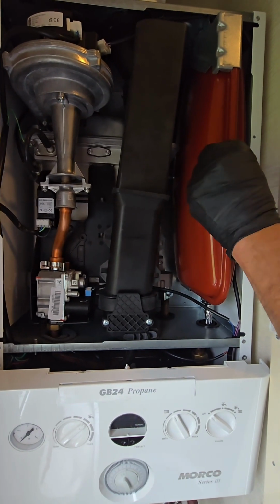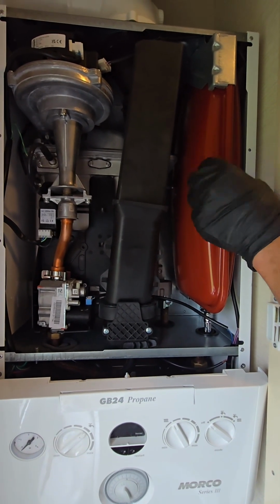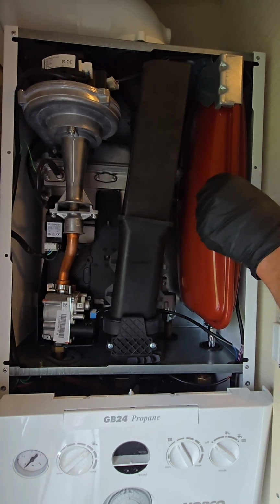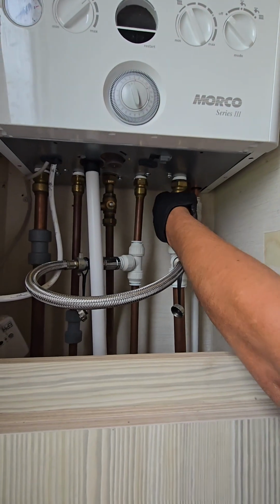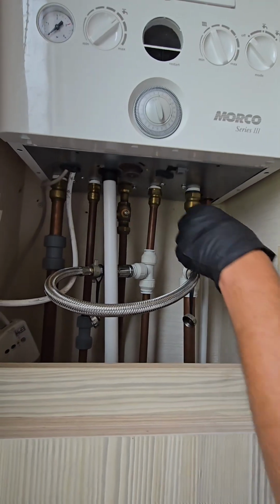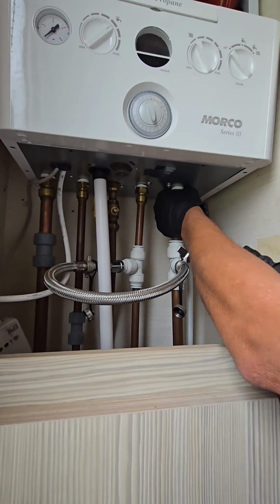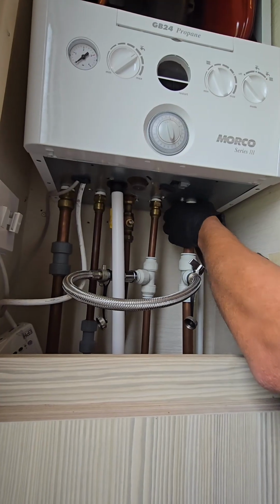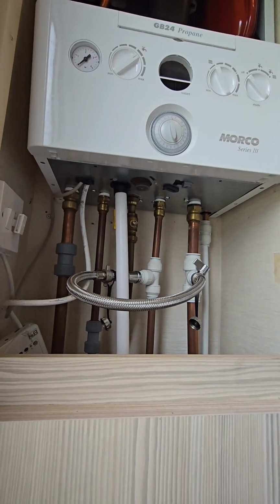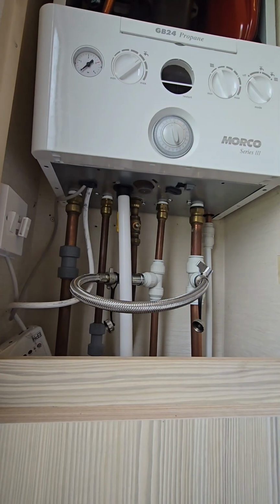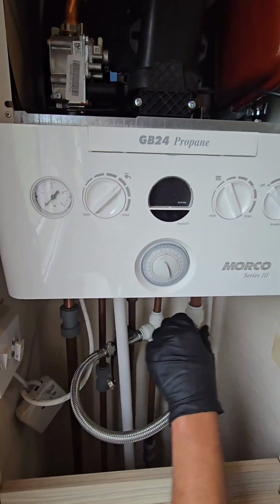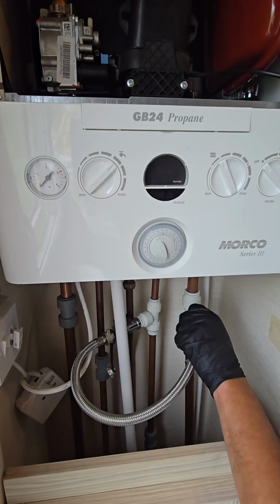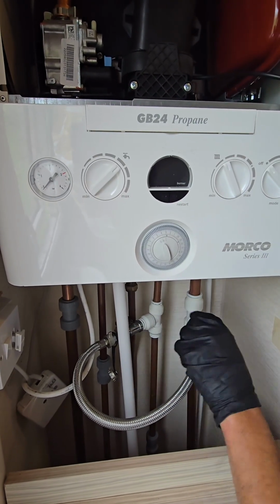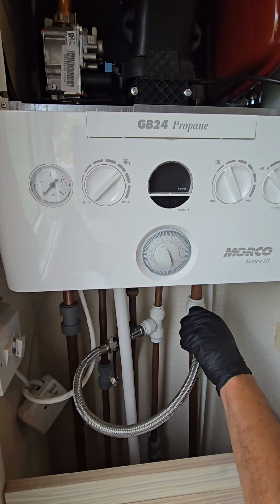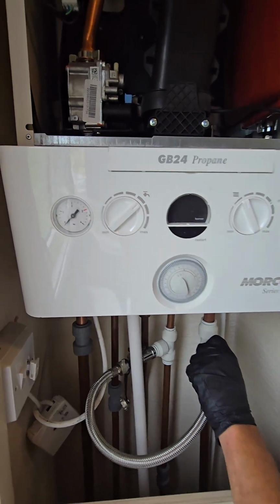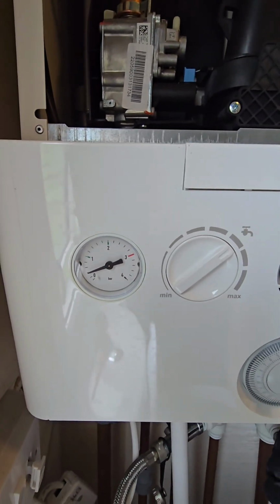Replace the Schrader cap. And that is the boiler fully drained and the vessel recharged. Remove the hose, close the drain point, and now we will top up the pressure. So open one side of the filling loop, open the other, and then we'll watch the pressure rise to 1.5.